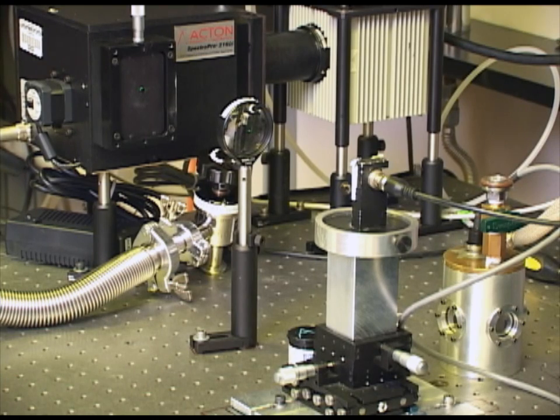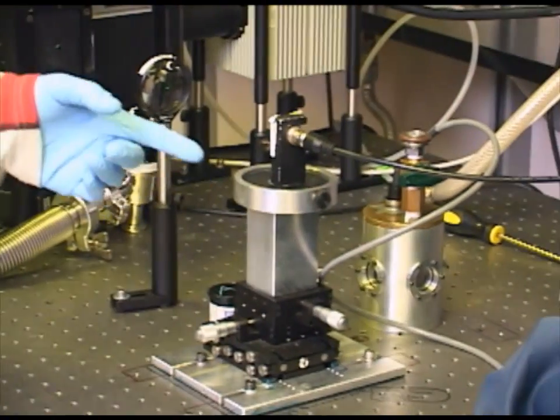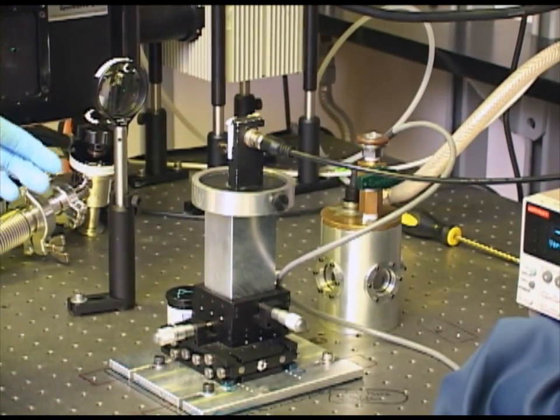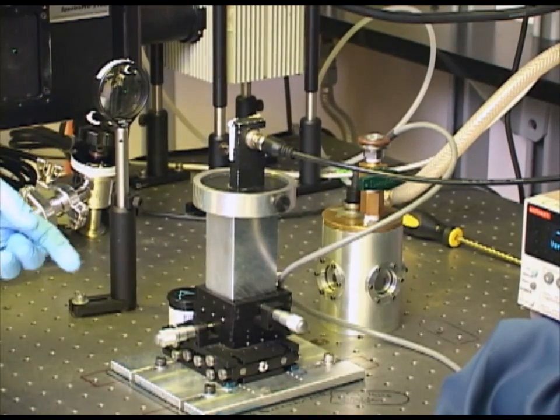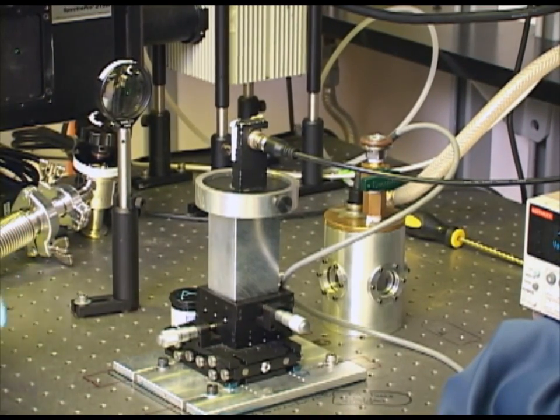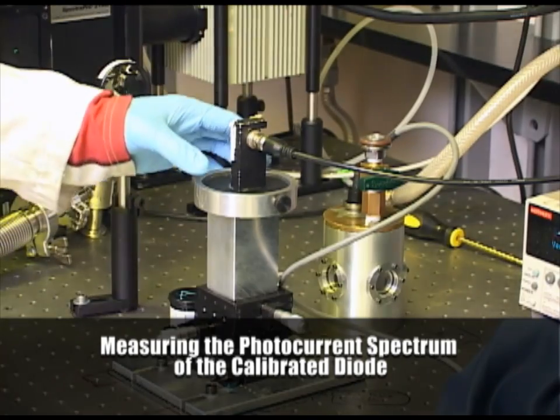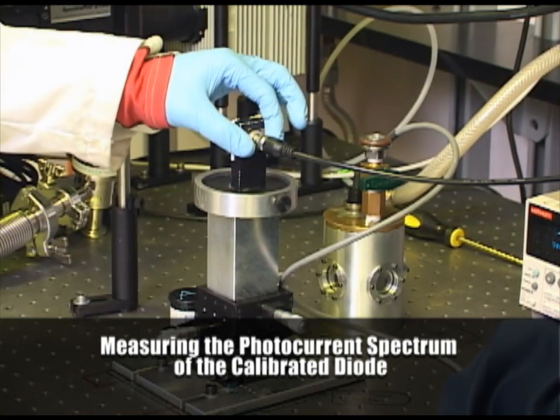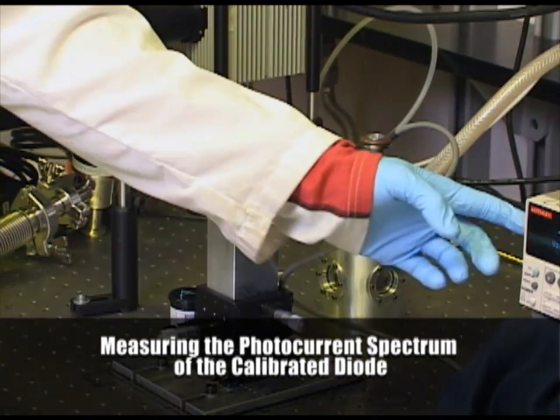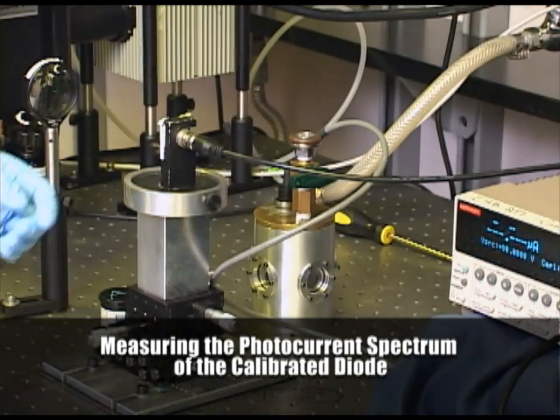In order to accurately determine the external quantum efficiency, we need to measure the photocurrent response of our calibrated diode, and then we'll need to measure the photocurrent response of our device under test. So to do this, we will take the calibrated photodiode, hook it directly into the source measure unit, and we actually have a mask for our photodiode.